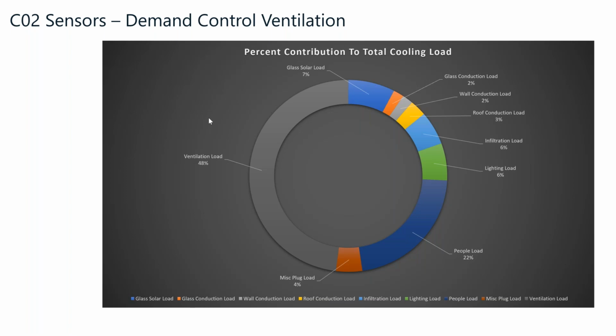The building itself has a ventilation calculation that, if you added up all the individual spaces — cafeteria, gymnasiums, auxiliary gym, auditorium, classrooms, locker rooms, etc. — has a ventilation requirement that would actually support, if you reversed out the math, more than 8,000 people in the building. Each individual space needed to be ventilated and have the ventilation capacity for that component. However, the students cannot be in more than one place at a time.